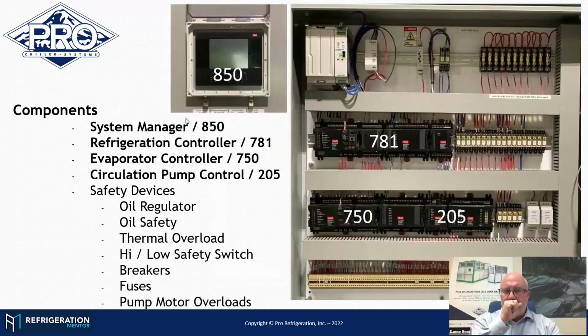Great. So I'm going to talk about from the component standpoint. I wanted to break it down at a controls level, and then I wanted to ID the controls on the system, then go into safety devices, because as we're doing troubleshooting on equipment, these are the things I find that if I can identify the major electronic controls components, then I know what the safety devices are. I know what the order of operations is expected to be. Now I can start to put things together when I'm in a troubleshooting diagnostics phase on the equipment.